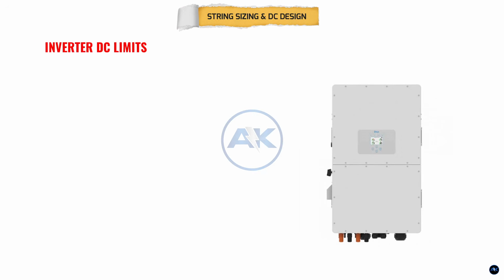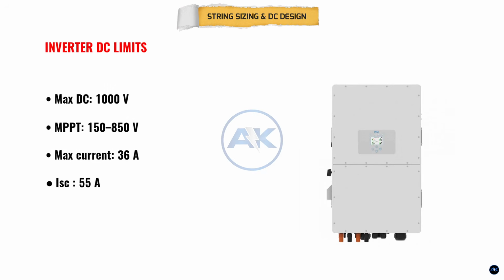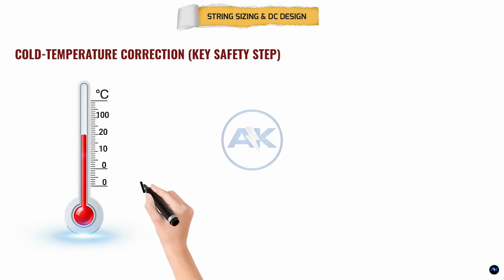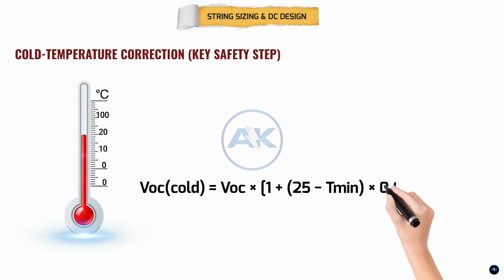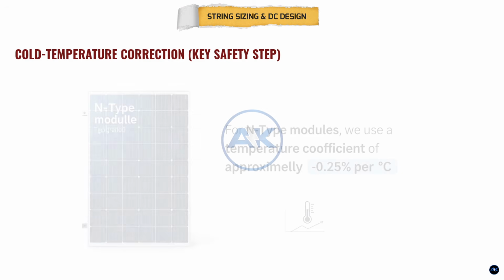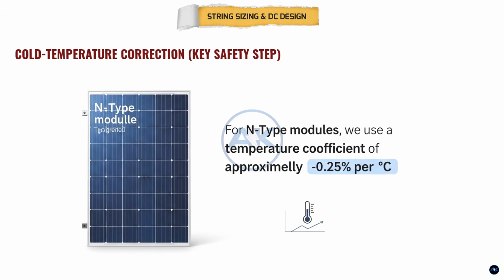The Deye 40-kilowatt hybrid inverter has a maximum DC voltage of 1,000 volts and an MPPT operating range between 150 and 850 volts. Each MPPT can accept up to 36 amps with a short circuit current limit of 55 amps. Solar panel voltage increases in cold weather, so we must apply a cold temperature correction to the panel's open circuit voltage. For N-type modules, we use a temperature coefficient of approximately minus 0.25% per degree Celsius.